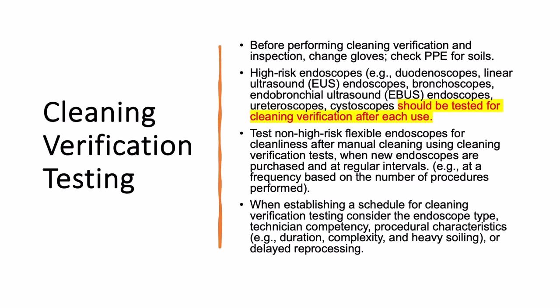When establishing a schedule for cleaning verification, consider the endoscope type, the technician's competency, and the procedural characteristics such as the duration, complexity, and heavy soiling, or delayed reprocessing. Some of you have carts that go around your facility where they'll bring the endoscopes to the emergency room or ICU, and you know they're not getting point-of-use treatment. You know that they could be sitting up there for hours and hours and hours. What we did in our facility when I was there was we would clean the scope according to the IFU, and then we would do cleaning verification. And if it failed, we cleaned it again and did cleaning verification again. And we did that until the scope came out clean. But follow your IFU and your endoscope manufacturer's instructions on what to do when a cleaning test fails.